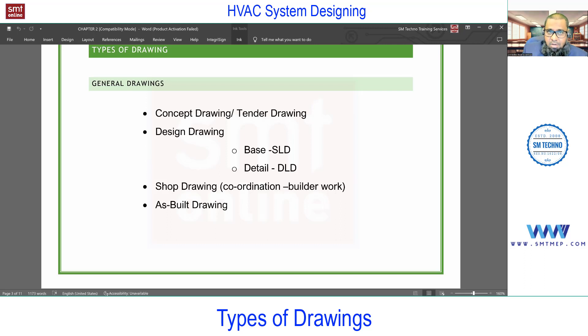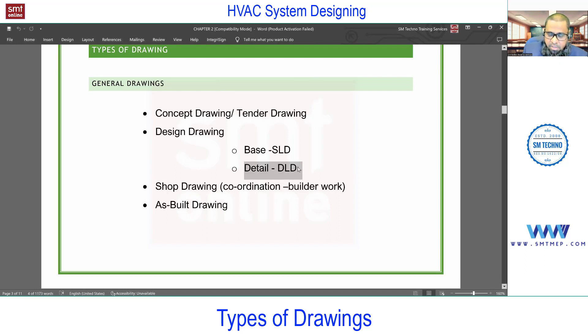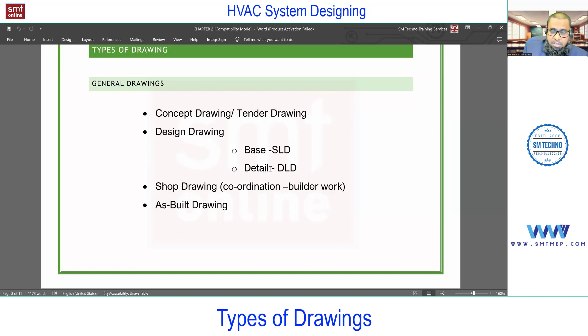The shop drawing can also be called an installation drawing. In the design detail drawing you'll find about 70 to 80 percent of the information. For big projects, work starts on site using the design drawing — about 60 to 70 percent of the work is completed with the design drawing — while the contracting company prepares the shop drawing in parallel, and the shop drawing is used in the final stage.